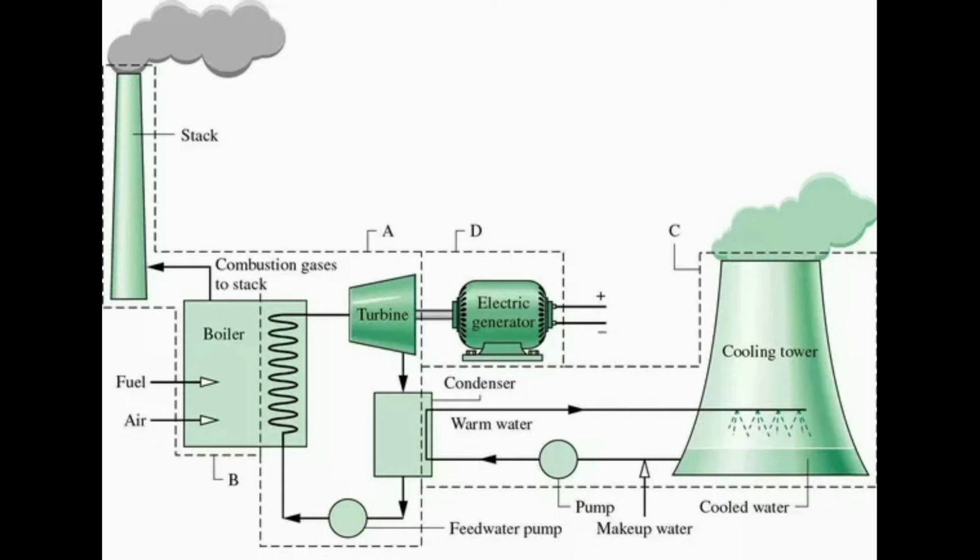It is not shown, but the coal hopper and coal pulverizer: coal is crushed into 25 mm pieces. These pieces are admitted into the boiler, and by the mills, they will be pulverized and turned into fine particles like face powder. So a fireball is formed, steam is formed in the upper layers of the tubes, and this is admitted into the turbine.